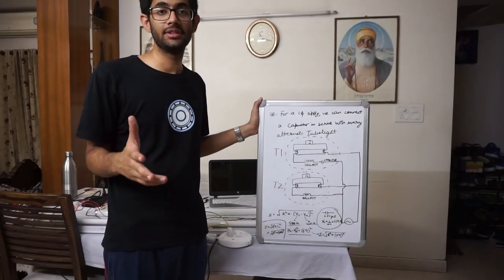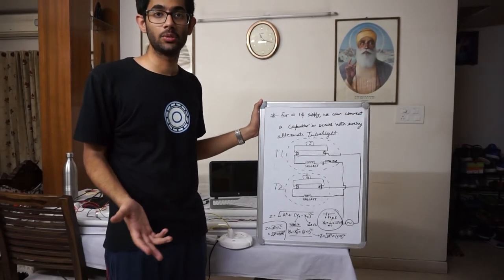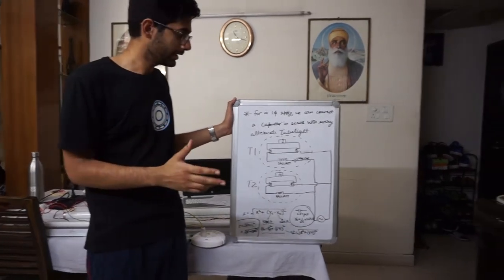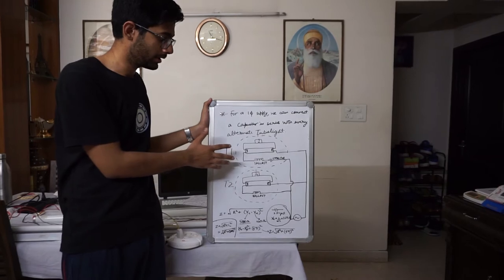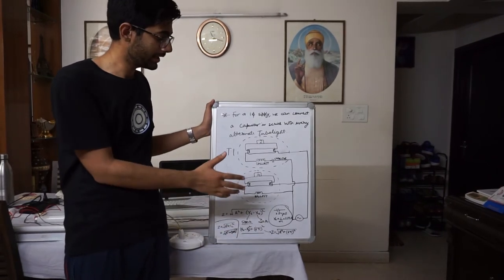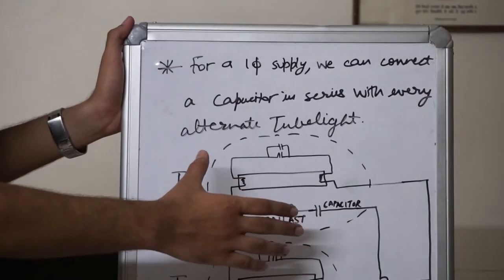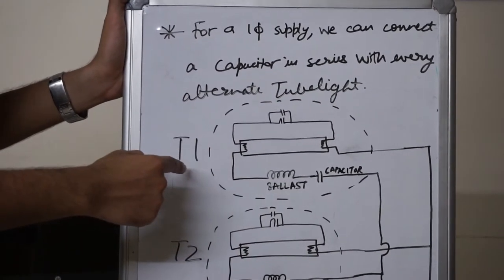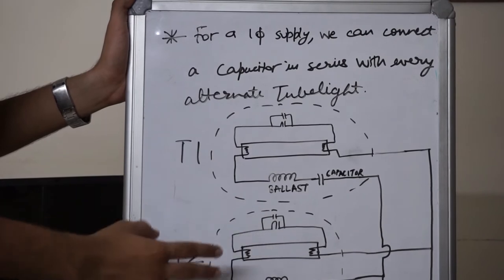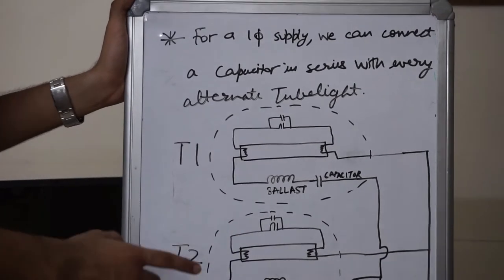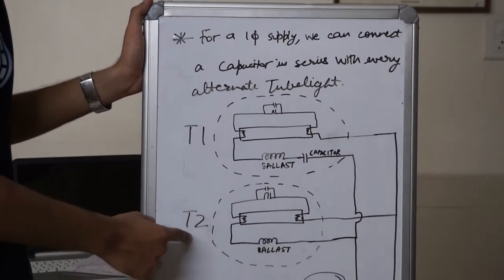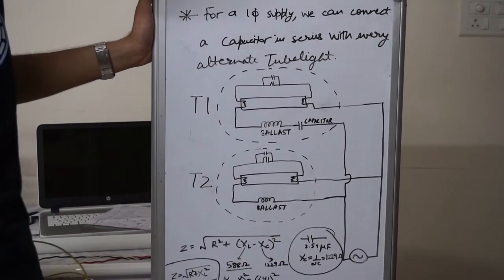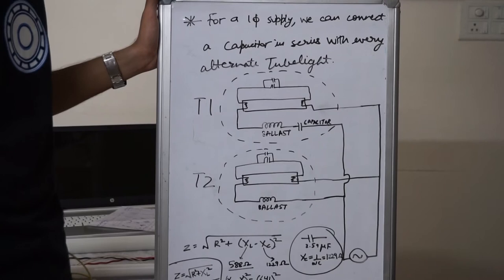If we have a single phase supply and we want to eliminate the stroboscopic effect, we can make use of capacitors. We can connect capacitors to alternate tube lights such that we have phase shift and the voltage reaching T1 is out of phase from the voltage of T2. So when the brightness of T2 is very low, T1 has some brightness and the net brightness is not zero, thereby eliminating the stroboscopic effect.